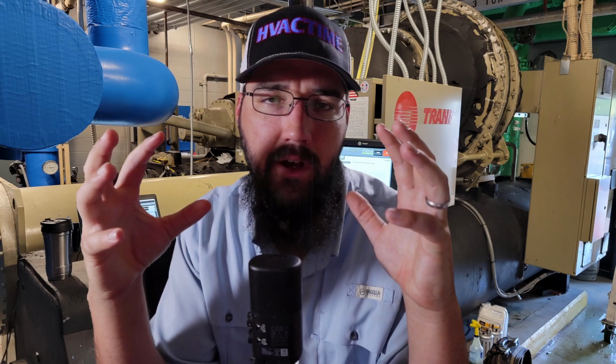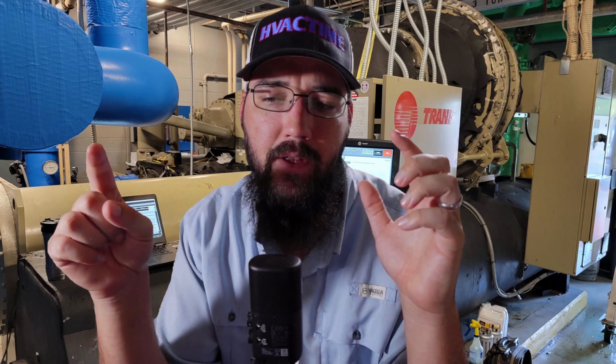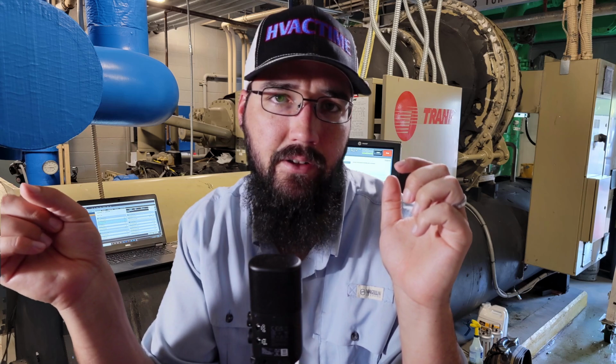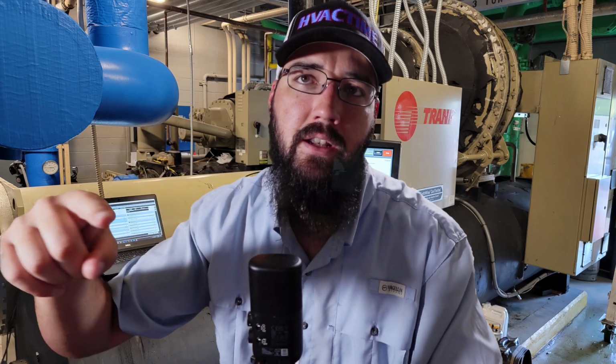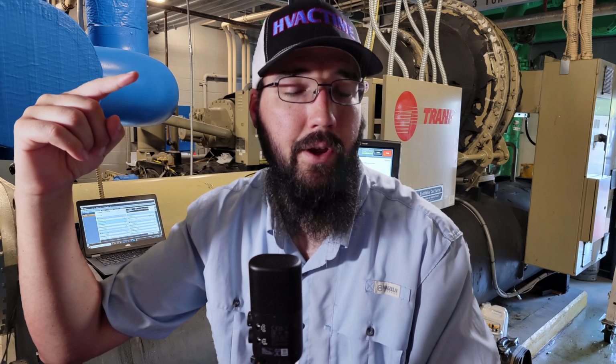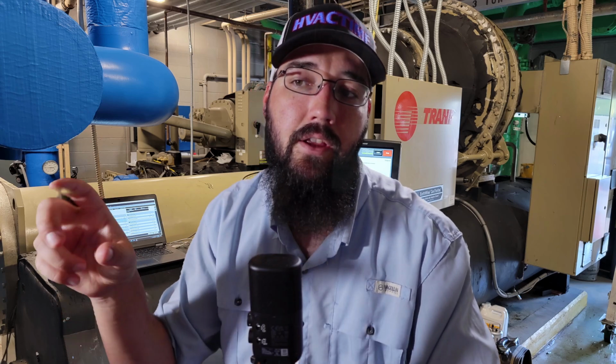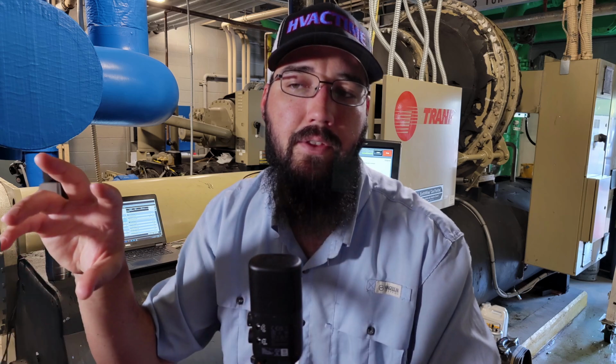That little canister at the bottom of the evaporator, they'll open the drain line and they'll open the vent line to the evaporator, and that will allow, because the evaporator vent line goes up to a higher point on the evaporator to where it's just vapor, that liquid at the bottom of the evaporator to drain into the gas pump chamber. And then after a certain period of time, we expect that so much refrigerant's gotten into that point, and we want it to be oil laden so we can get that refrigerant back.